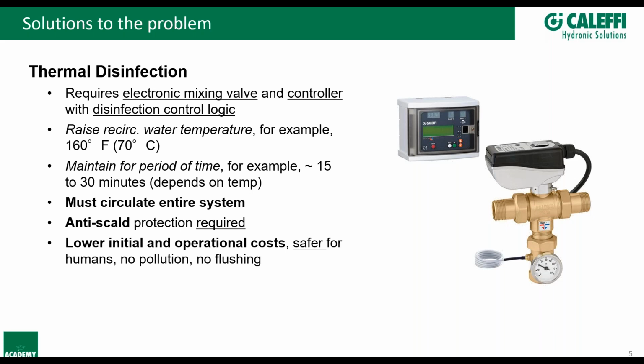Thermal disinfection obviously needs a domestic hot water source, which you're already going to have, and your distribution system as well. But you're also going to need some kind of controller with logic that can handle this whole process. That's where our LEGIOMIX comes into play, which I'll talk about in another slide—you can see it there on the right. But you're going to need some form of electronic mixing valve.